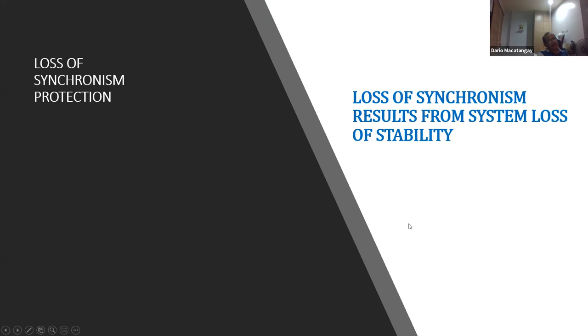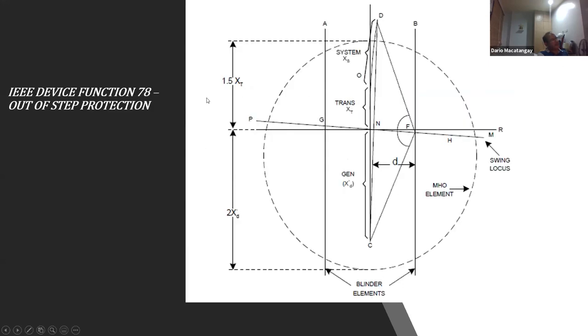Loss of synchronization is covered by function 78, which is out of step protection. Again, this is a Mho circuit. When you have a fault in the system and that fault is interrupted right away, it's considered a stable swing. There are two types of swing: the first is a stable swing, the second is an unstable swing. With a stable swing, the impedance will swing when there is a fault, but if it is cleared right away by the transmission system, then it's a stable swing.